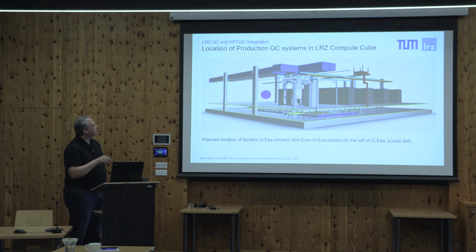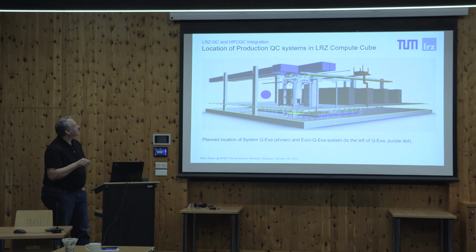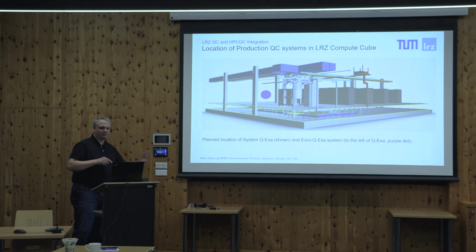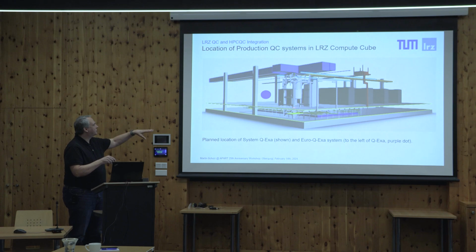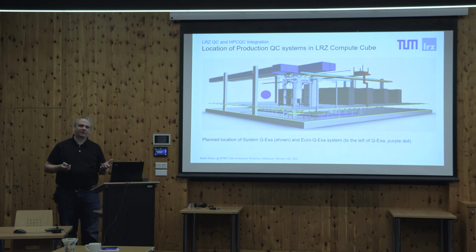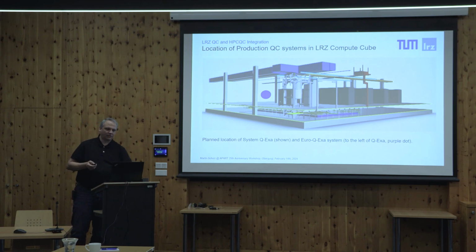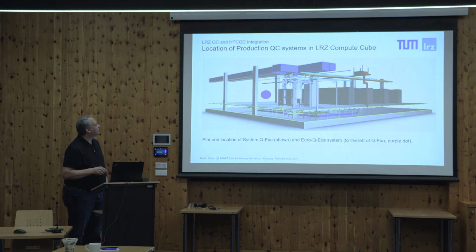So these are standard racks over here where we have several big standard clusters. And we are actually starting to place quantum systems directly, not just in the integration center, which is a lab environment, but directly into the compute floor. You cannot put them onto the raised floor, which we typically have, because there are vibrations, so you need to put them down in the foundation part. You need to have compressors and all the cooling mechanisms there.